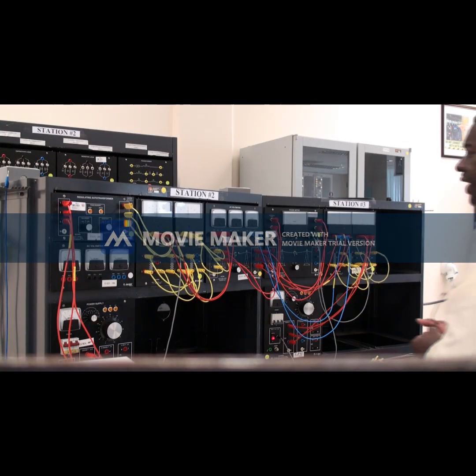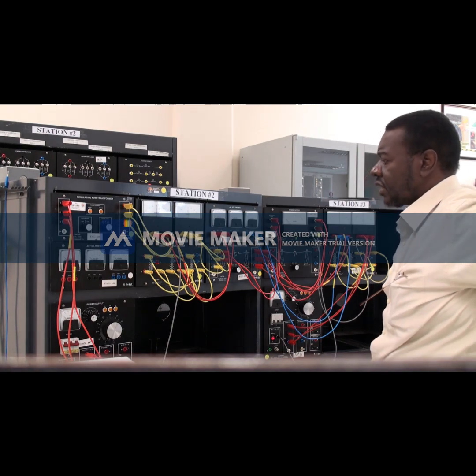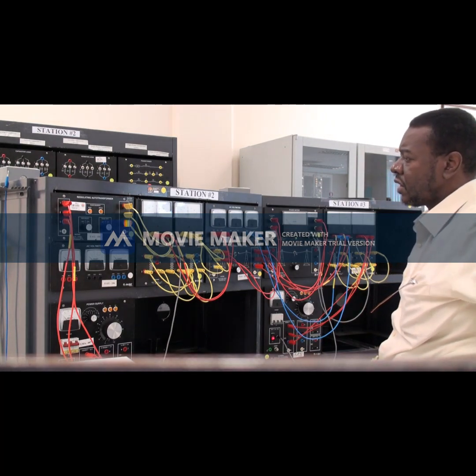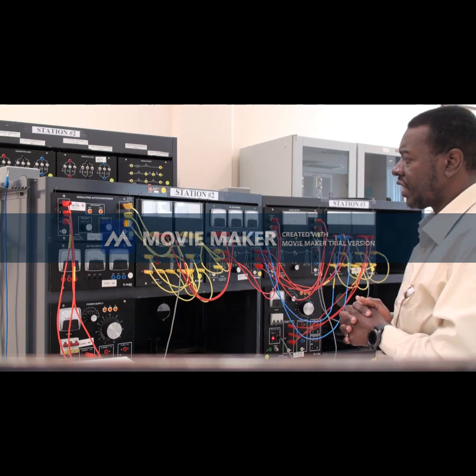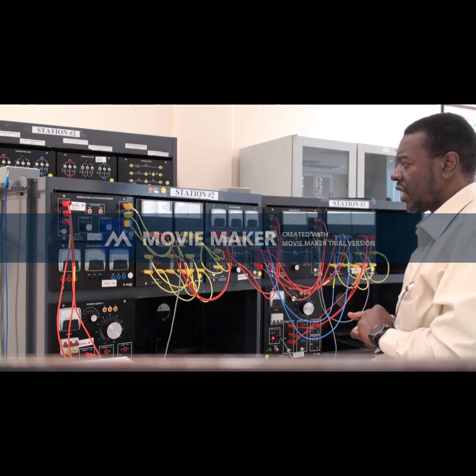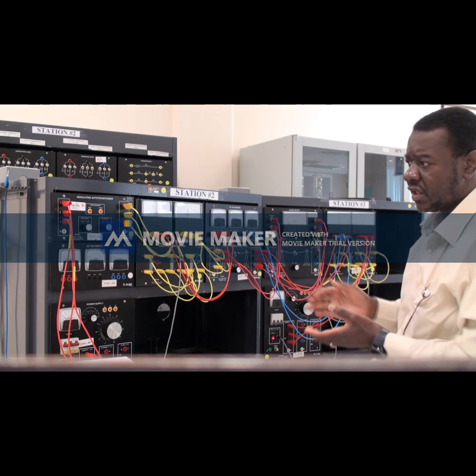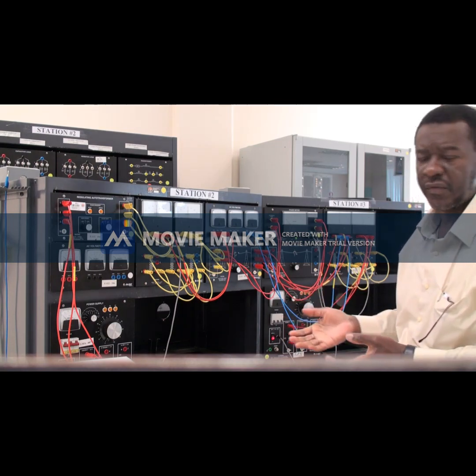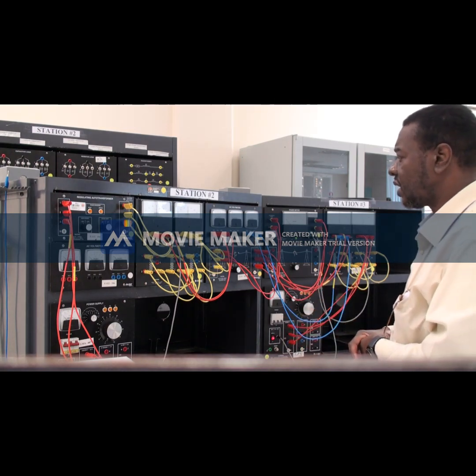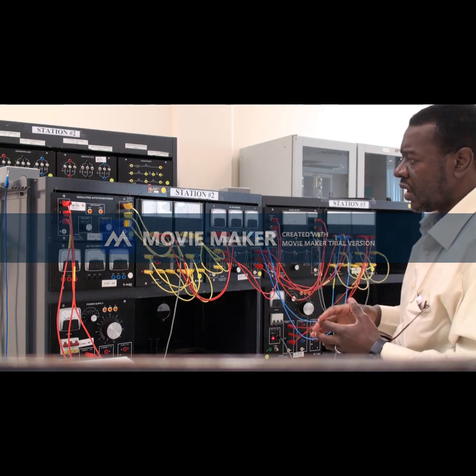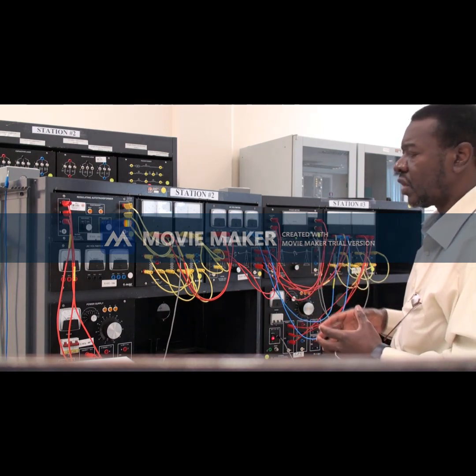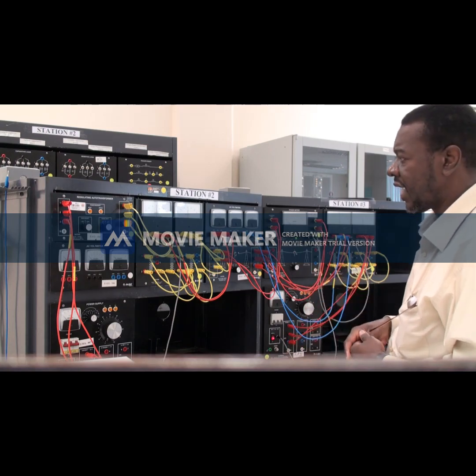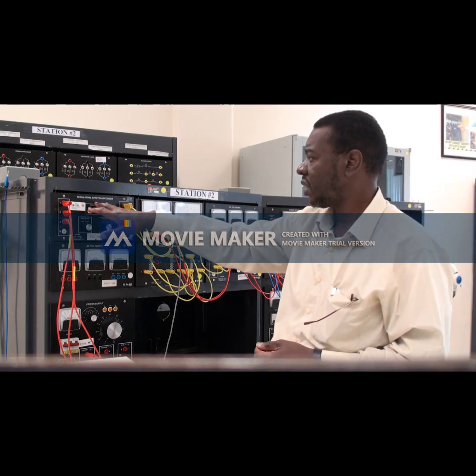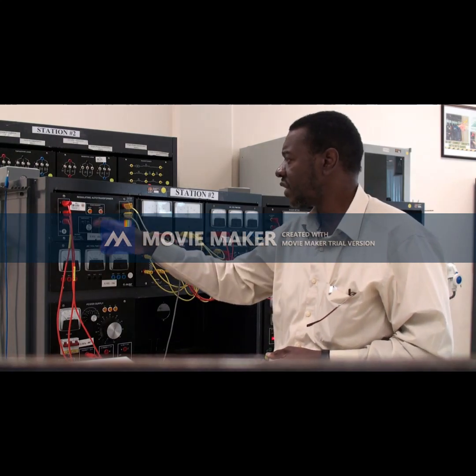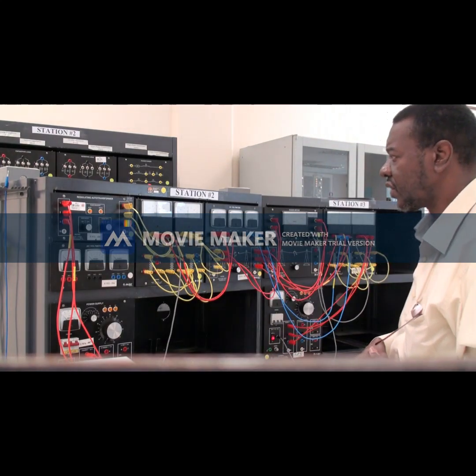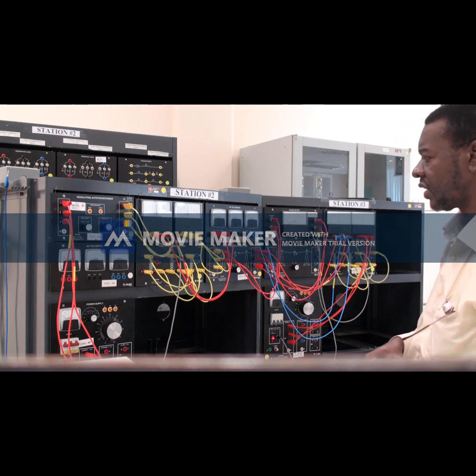Okay, we're back. The second scenario we are going to demonstrate is the flow of real power. In the second scenario, if we have equal voltages but they are not in phase, then real power will flow. To demonstrate that, we introduce a new instrument to shift the angle. So we have here the new regulating transformer. This regulating transformer is used just to shift the phase, plus and minus 15.